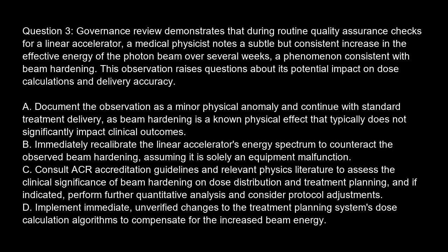Question 3. Governance review demonstrates that during routine quality assurance checks for a linear accelerator, a medical physicist notes a subtle but consistent increase in the effective energy of the photon beam over several weeks, a phenomenon consistent with beam hardening. This observation raises questions about its potential impact on dose calculations and delivery accuracy.